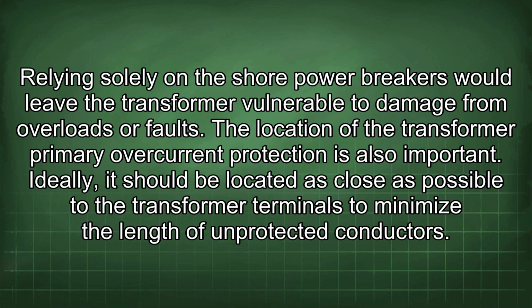The location of the transformer primary overcurrent protection is also important. Ideally, it should be located as close as possible to the transformer terminals to minimize the length of unprotected conductors.